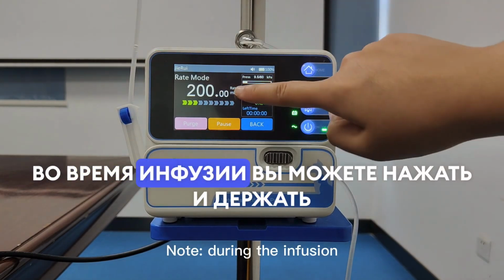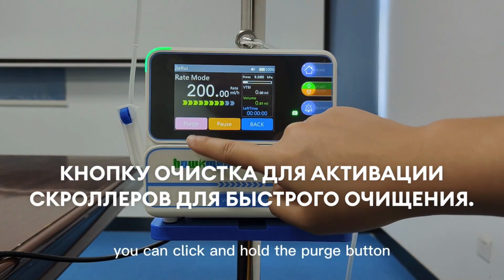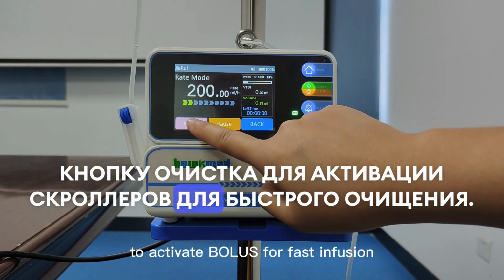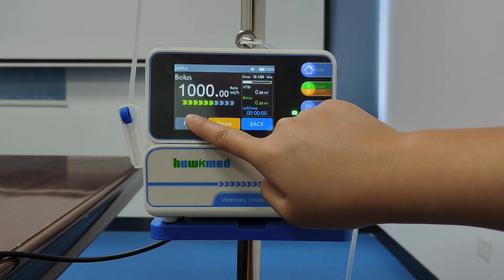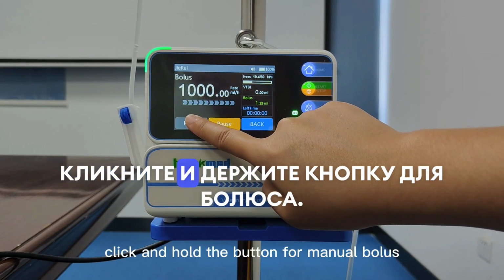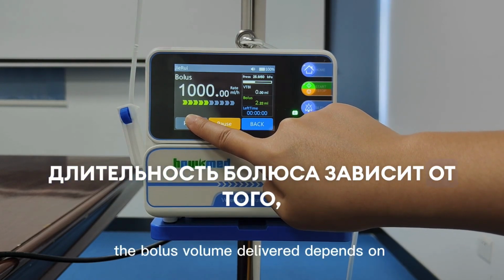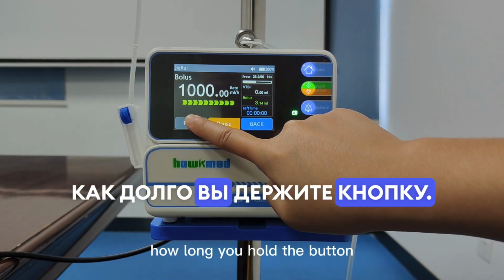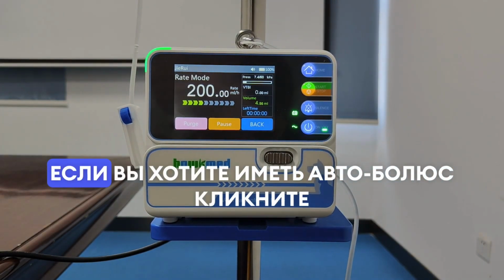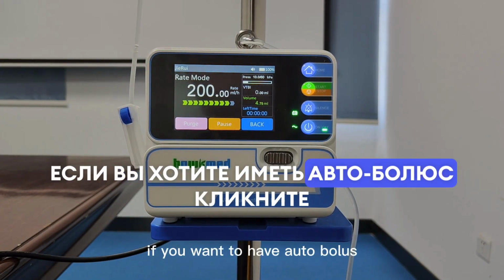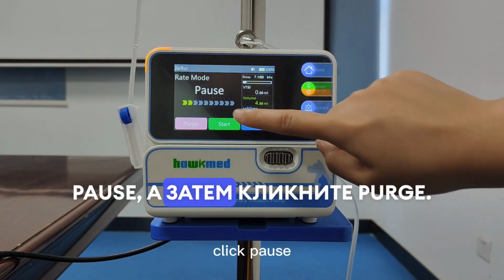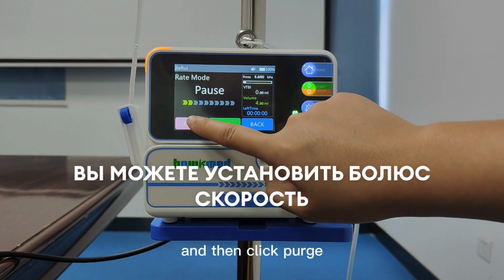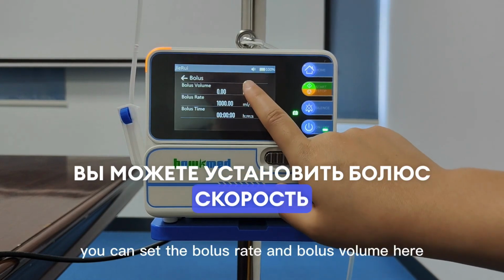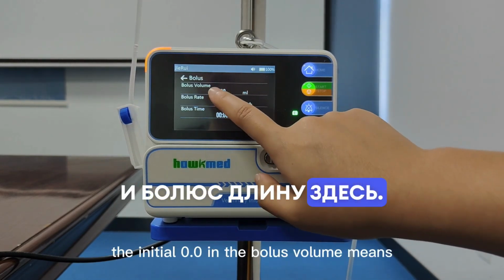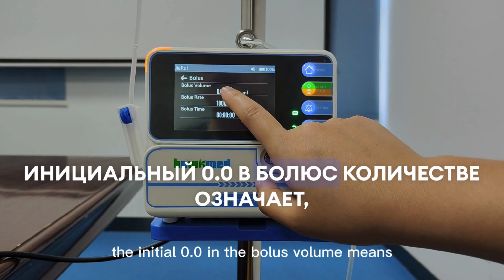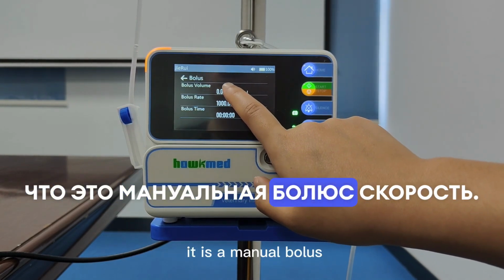Note, during the infusion, you can click and hold the purge button to activate bolus for fast feeding. Click and hold the button for manual bolus. The bolus volume delivered depends on how long you hold the button. If you want to have auto bolus, click Pause and then click Purge. You can set the bolus rate and bolus volume here. The initial 0.0 in the bolus volume means it is a manual bolus.